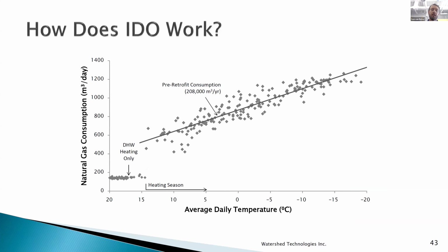So how does this work? The gray points here are typical; each point represents a day of gas consumption. And on the x-axis, you have the outdoor temperature. As you'd expect, gas consumption increases as it gets colder outside, but you really see this huge disconnect between when you're only heating domestic hot water in the summer and when you start heating space. There's this huge jump in energy use, and we call that the overhead. So when we see that, we know that this building is overheated.